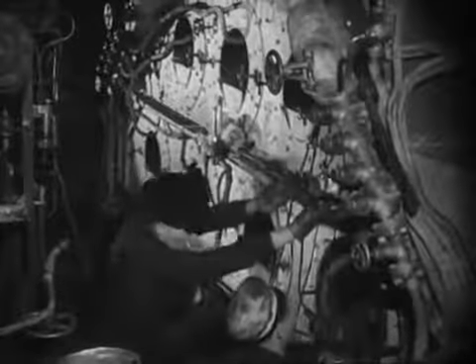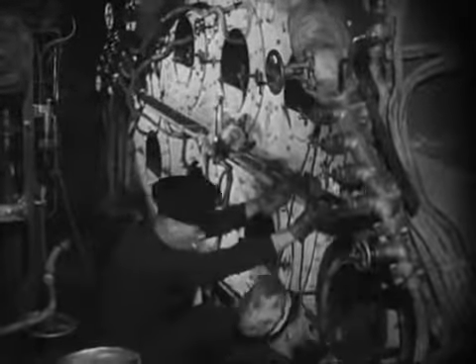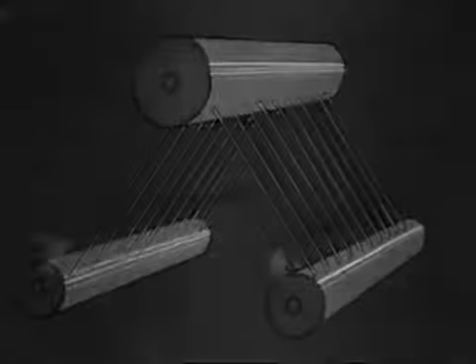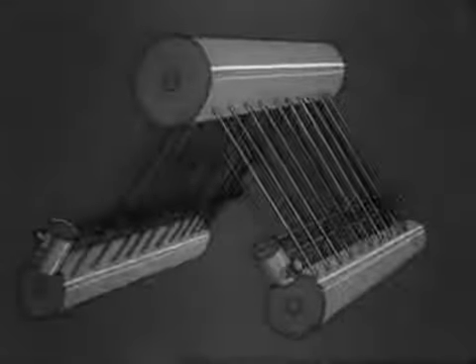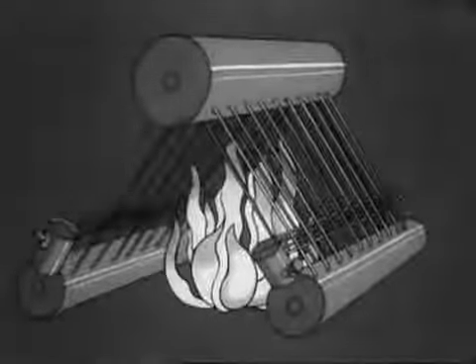To the uninitiated, a boiler room just looks a maze of pipes, taps, and valves. So let's get a clear idea of what it's all about. An Admiralty 3-drum boiler consists of an upper circular steam drum connected to 2 lower water drums by nests of tubes, the whole forming a letter A. Superheaters with their tubes are fitted between the outer and inner row of tubes on each side of the boiler. We'll deal with them later. The triangle between the nests of tubes forms the furnace space.